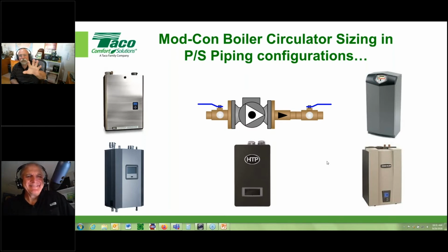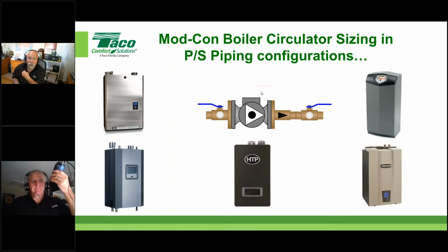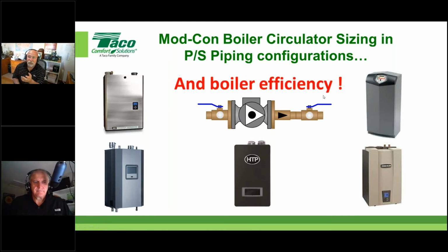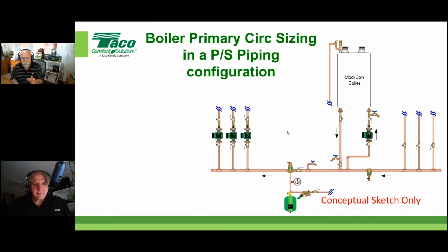What we're going to talk about now really focuses on the fact that this is a very important part. See the circulator? I'm showing a bunch of different condensing boilers here. Not that we want to step on anybody's toes or forget anybody. Just understand the circulator, when we're talking about sizing it as a primary or a boiler pump, is very important to the overall efficiency of the system, right? And it does have impact and it can have an effect. So that's what we're going to focus in on. What our focal point's going to be.